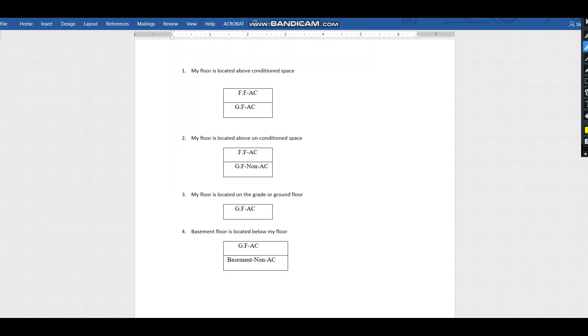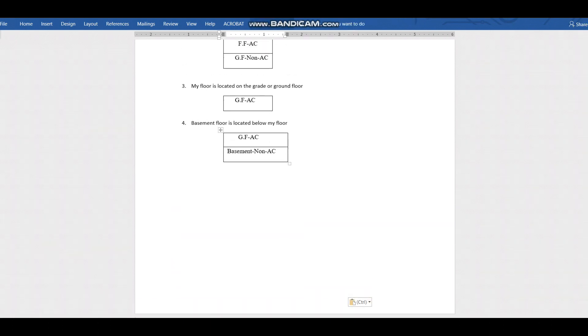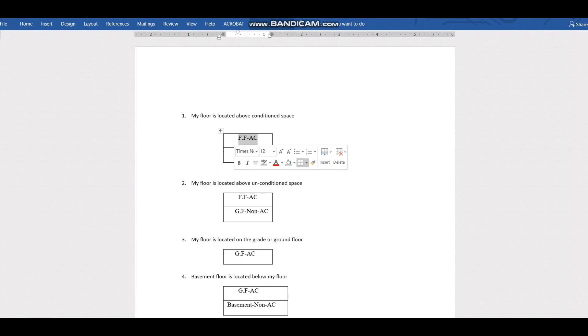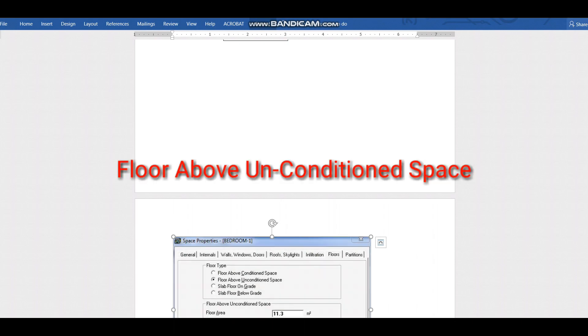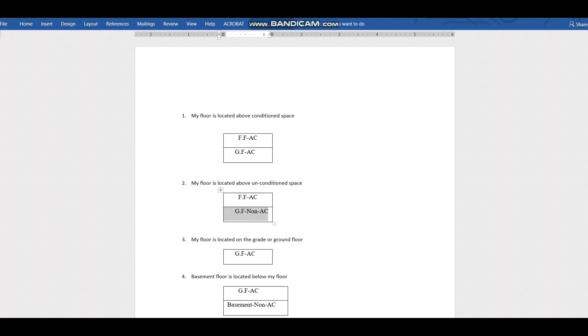For 'floor above conditioned space,' read it as: my floor is located above conditioned space. For example, if you're on the first floor doing the HAP calculation and the ground floor is also an AC area, then your floor is above conditioned space. For 'floor above unconditioned space,' your first floor is AC but the ground floor below is a non-AC area, so there will be significant heat load transfer through that floor.